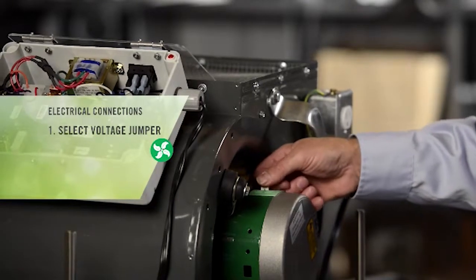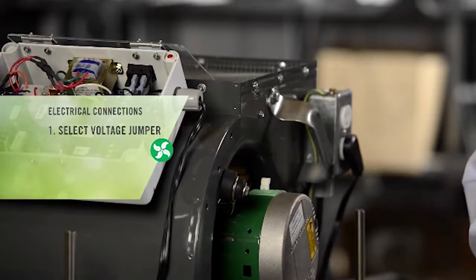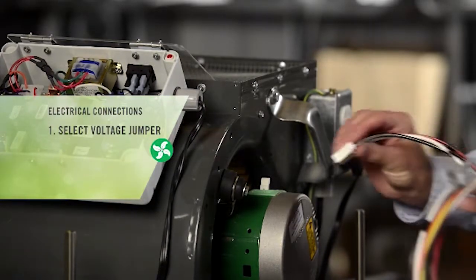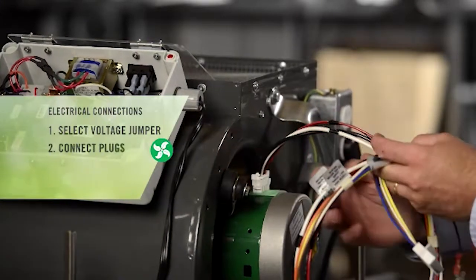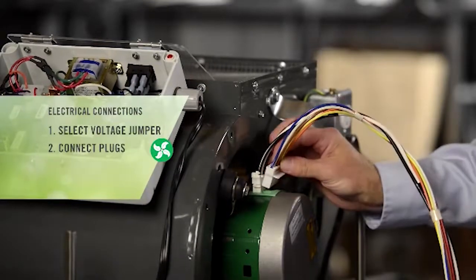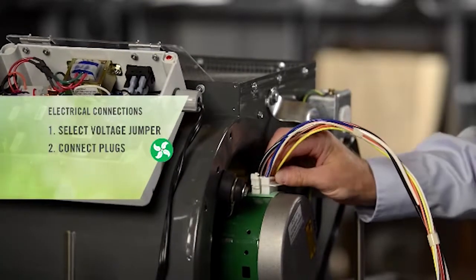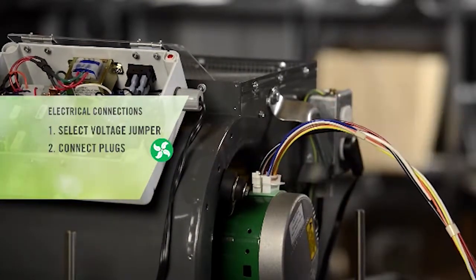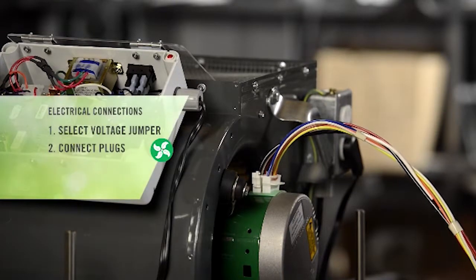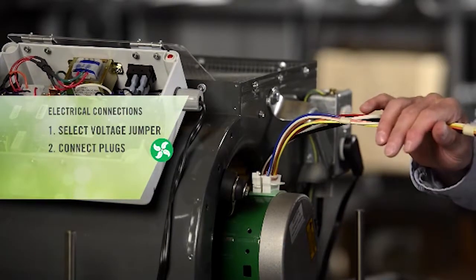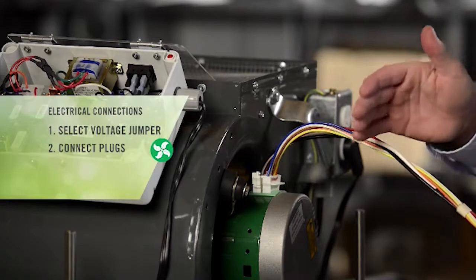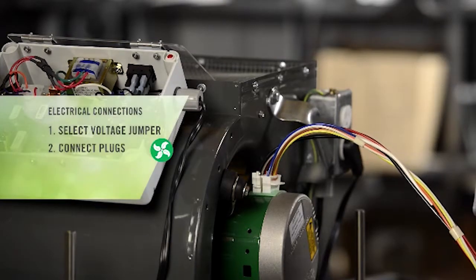Again, I strongly recommend you put the jumper in the motor first and then connect the 2 harness plugs. After I get the 2 harness plugs into the Evergreen IM motor, you now see why it's a good idea to put that voltage jumper in first. Now we have 42 inches worth of leads to connect the Evergreen IM to our HVAC system.